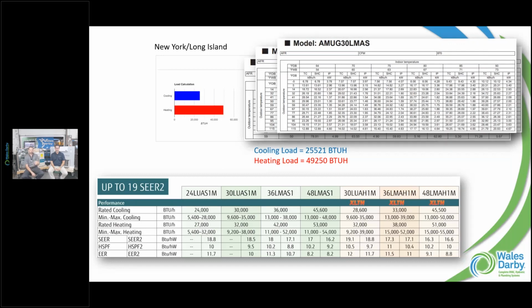In this case, we looked at a 2.5-ton system. For that same capacity, and you should be able to zoom into this at home, so I'm not going to go nuts with the pointer, on an 86-degree day, when I come over to that 70-degree column, I'm getting about 29,000 BTUs out of this machine. So I get 4,000 BTUs more than what I need. I'm going to cover the entire cooling load here, and that's where I'd rather see the 2.5-ton system go in.